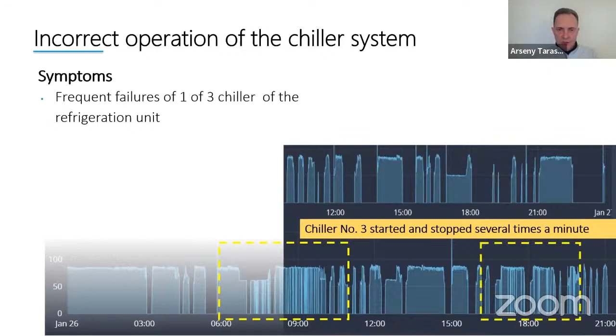Another example is a project we realized at one of the chilling warehouses, where the temperature should have been maintained at minus 18 degrees. From the users' standpoint, everything was okay, except one of the chillers was running out and had to be repaired much more often than the other two. It looked like there were too many peaks in energy consumption, and energy consumption of that particular warehouse was higher than similar equipment in a different building. So they couldn't understand what was going on.